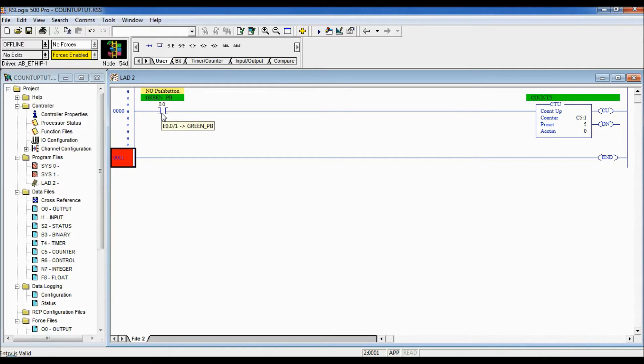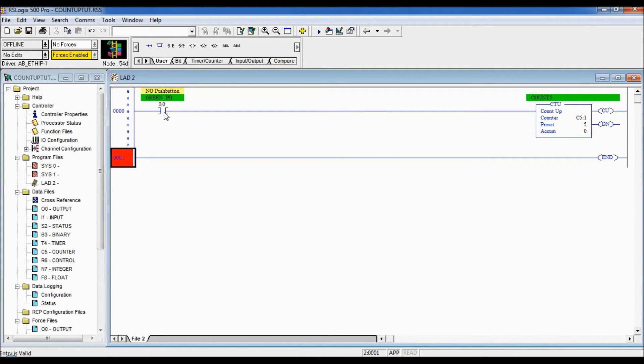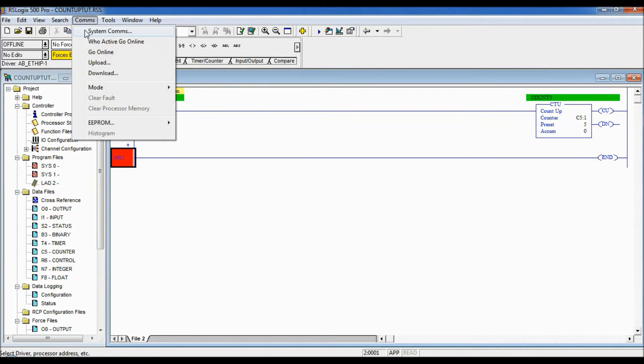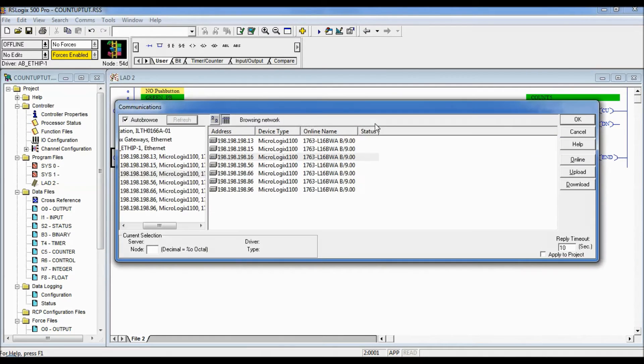So every time that this green push button is pressed it would go from false because it's normally open and when I press it it would go true so this counter should count and should not count again until I let go of that push button. So we'll download that right now into our controller.